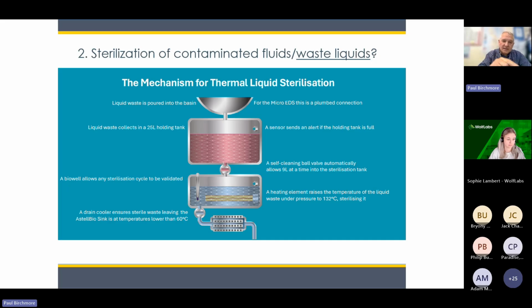And underneath that is a secondary chamber, which we call the kill tank, and that effectively is the alternative to an autoclave. That's the high pressure, high temperature section of this process. So that bit takes that liquid up to 100 and whatever for 20 to 30 minutes, reaches those sterilization temperatures, allows you to ensure you've killed the bacteria, all the proteins are denatured, and then it can just flow automatically to the drain. So the practicalities of this, there are some angles where you could look at the practicalities of loading an autoclave, unloading an autoclave. This one, you just pour the liquid in at the top and it flows out immediately into the drain at the bottom.